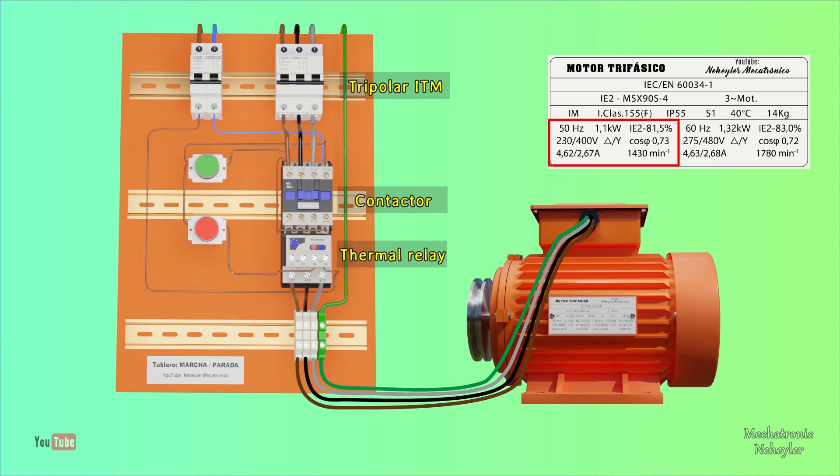For the control circuit, you can safely use 16-gauge wire and a 10-amp bipolar ITM. The explanation of each of these elements had already been made in previous videos, which I will leave here at the end so that you can review it.